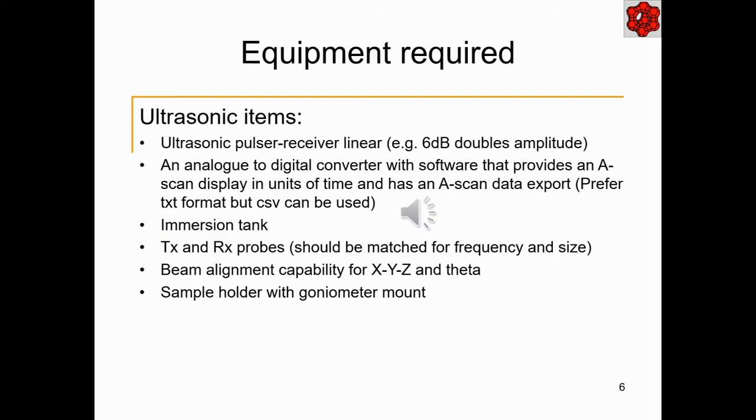In order to use the MAPIS template, you are going to need to have hardware that can capture ultrasonic waveforms. This will include an ultrasonic pulser-receiver that is linear, that is doubling in amplitude for every 6 dB added, an analog-to-digital converter with software that provides an A-scan display in units of time and has an A-scan data export, preferably TXT format. However, CSV can also be used.